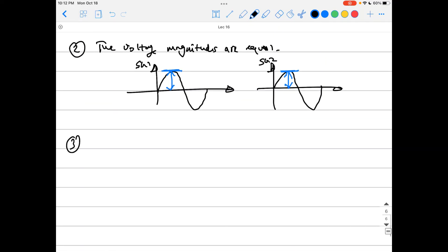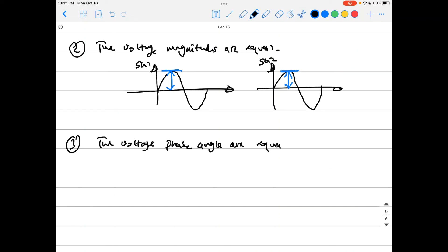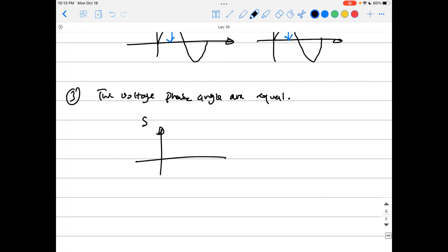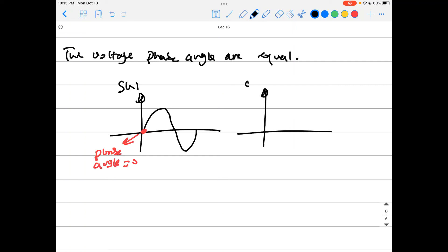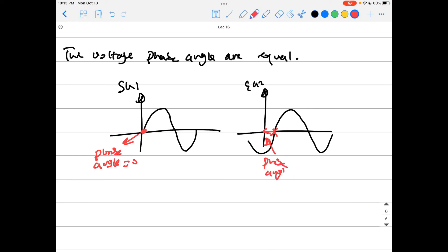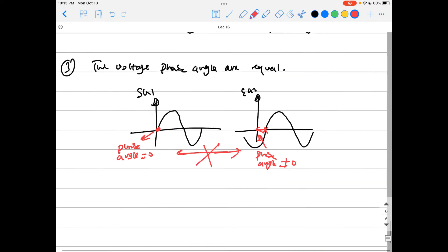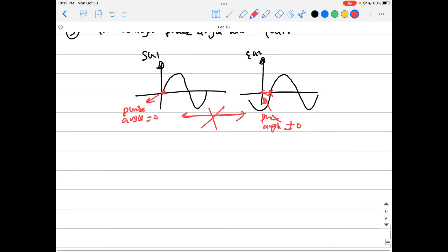Condition number three: the voltage phase angles must be equal. You cannot have one generator's waveform starting at zero phase angle and the other at a different phase angle — they would not be identical. You must ensure the phase angles of all generators to be connected are equal.